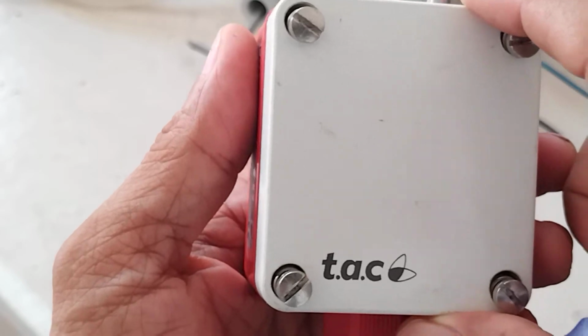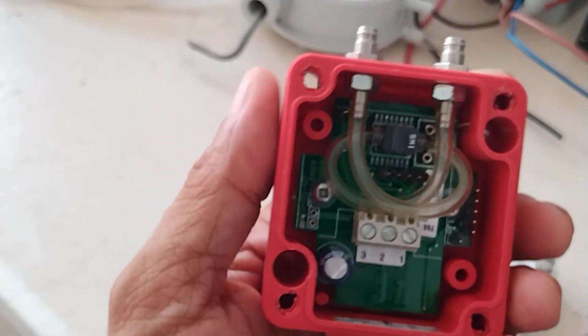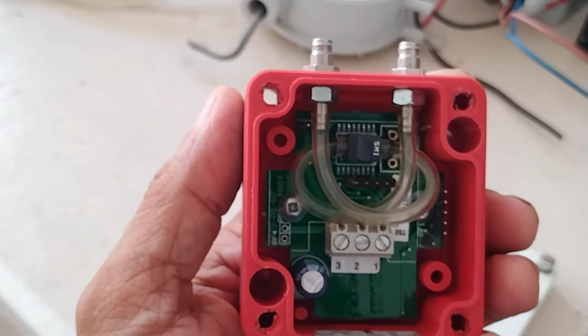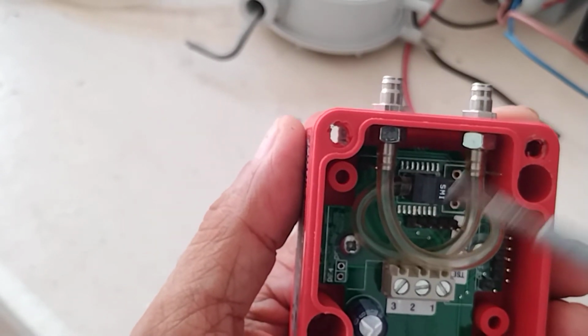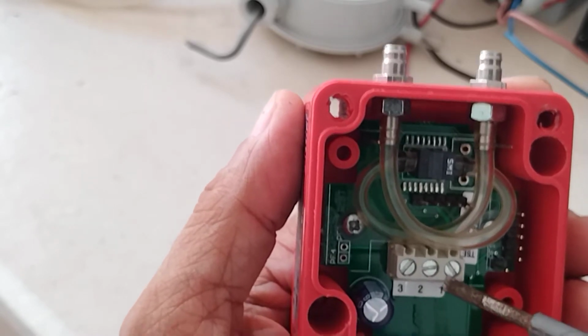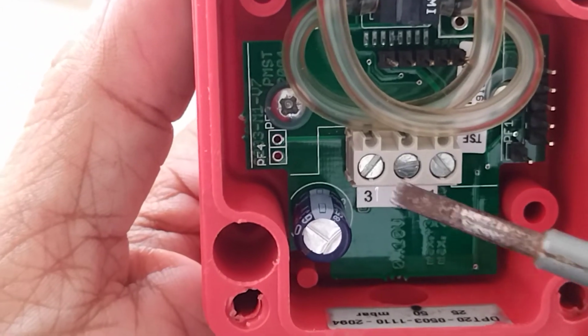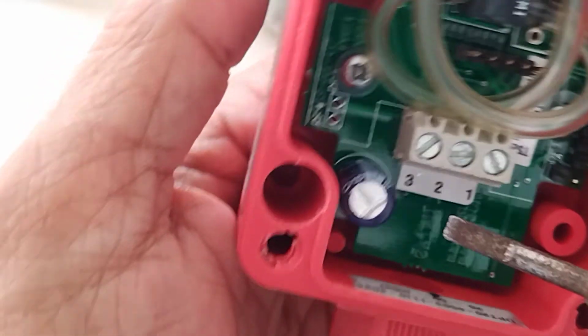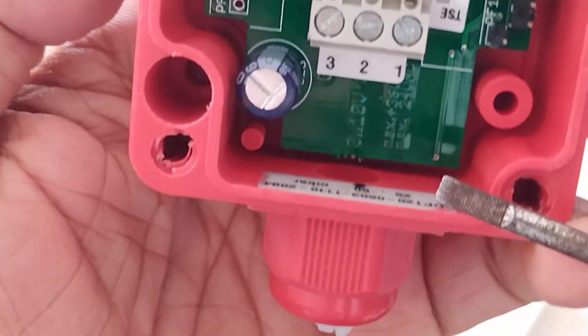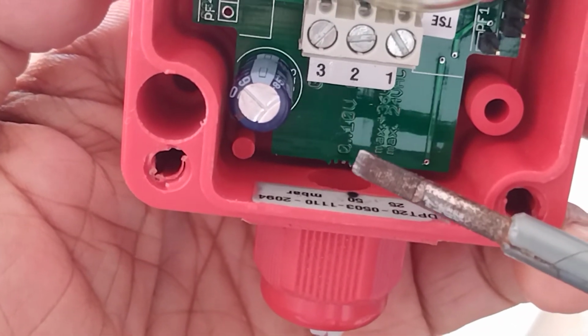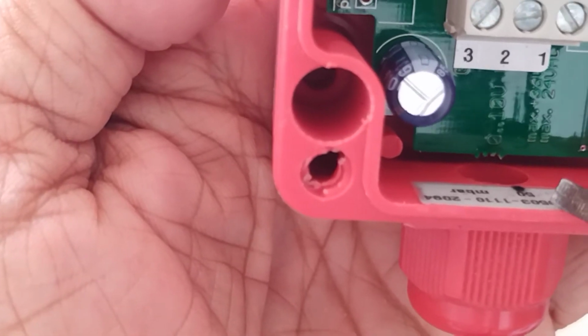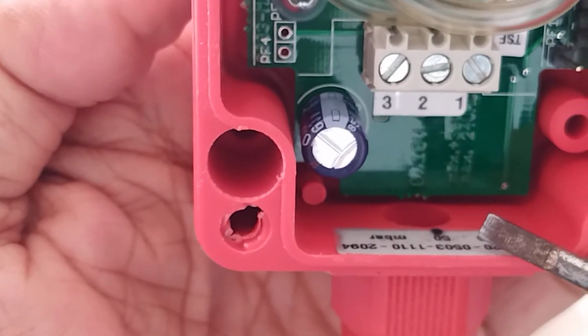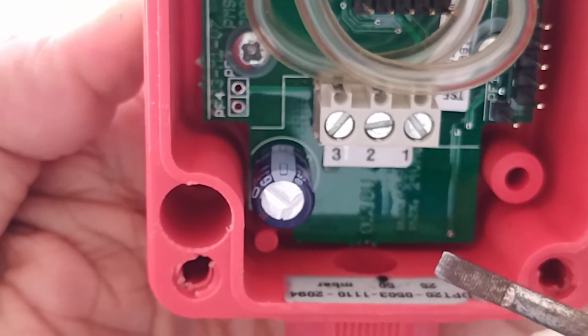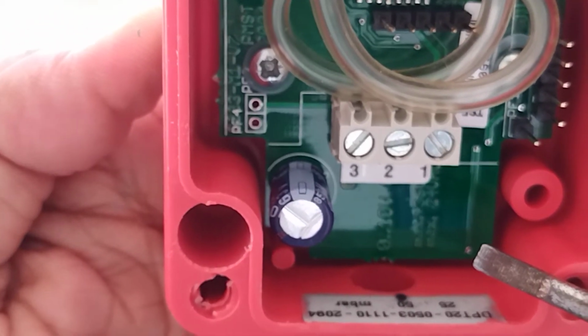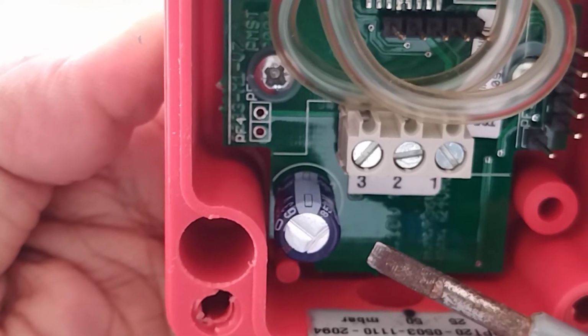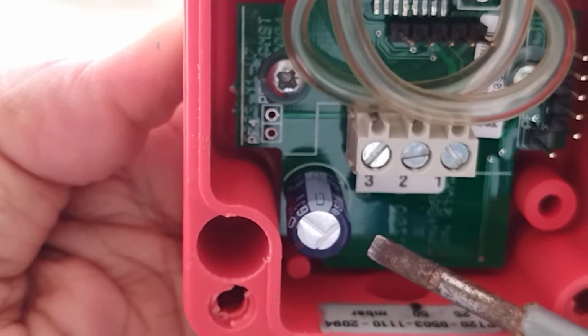Now let's try to open this and see what the terminals inside are. As you can see here, there are 3 terminals: 3, 2, 1. Based on what is written here, terminal 2 says 0 to 10 volts, then 1 is the 24 volts AC, then 3, obviously, will be the common.